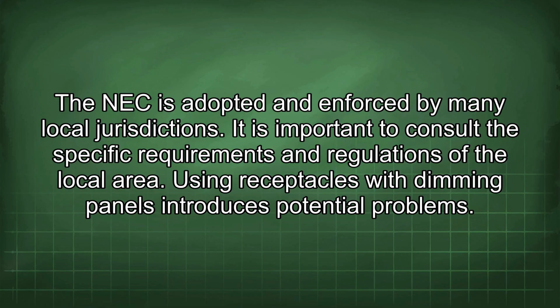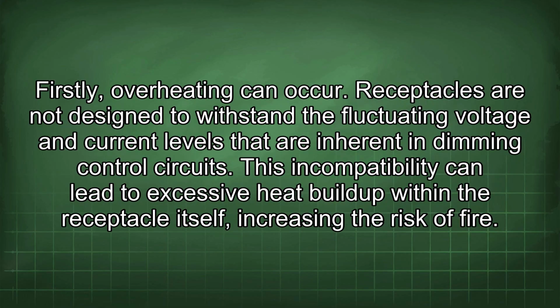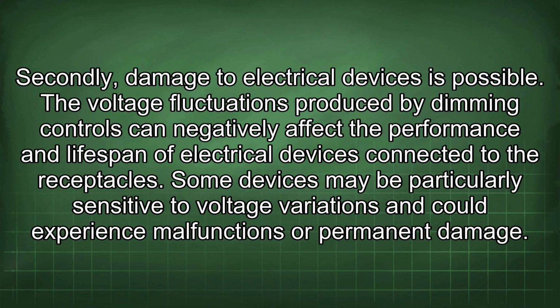Using receptacles with dimming panels introduces potential problems. Firstly, overheating can occur. Receptacles are not designed to withstand the fluctuating voltage and current levels that are inherent in dimming control circuits. This incompatibility can lead to excessive heat buildup within the receptacle itself, increasing the risk of fire. Secondly, damage to electrical devices is possible. The voltage fluctuations produced by dimming controls can negatively affect the performance and lifespan of electrical devices connected to the receptacles. Some devices may be particularly sensitive to voltage variations and could experience malfunctions or permanent damage.